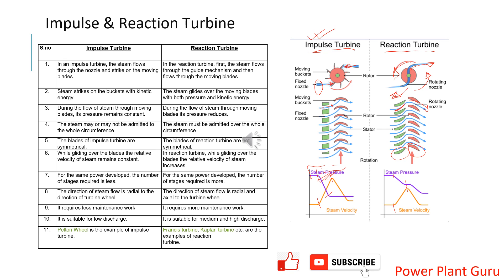This is how the impulse turbine is designed — use high-pressure steam to get high velocity, impinge it on the turbine blades, and get rotational speed. This is most useful where the turbine is using very high pressure steam. In an impulse-plus-reaction turbine setup, the impulse stages must be in the first few stages where steam pressure is highest. So wherever you have an impulse turbine in a modern setup, it will be in the first few stages.